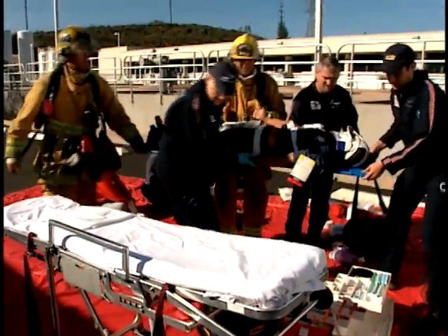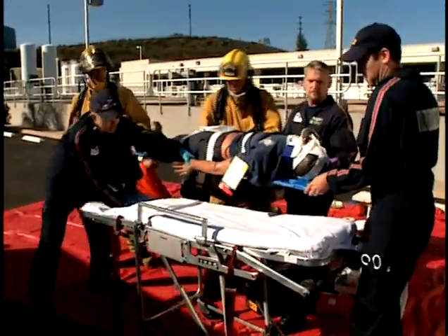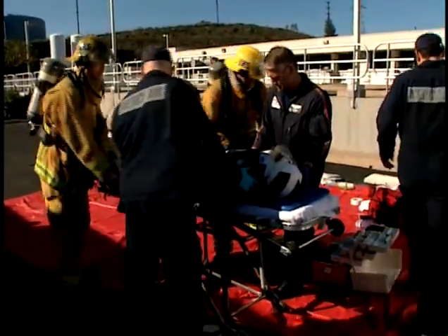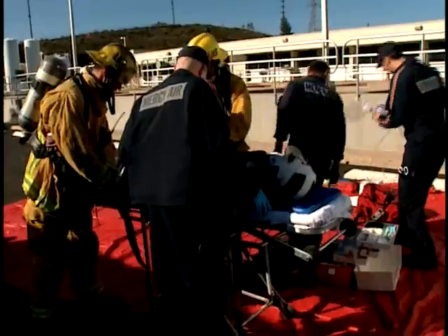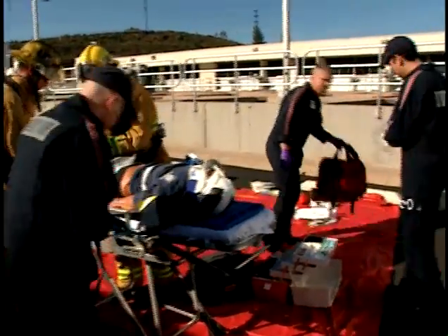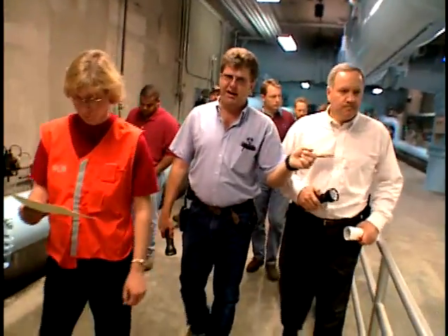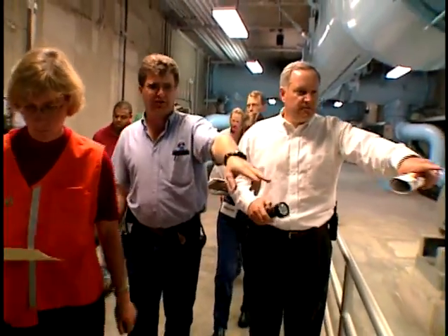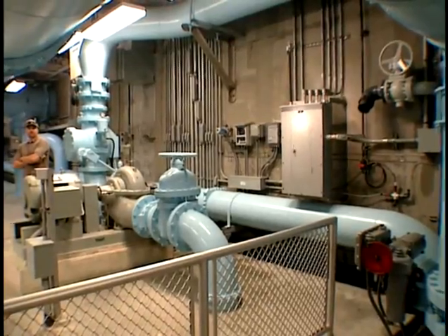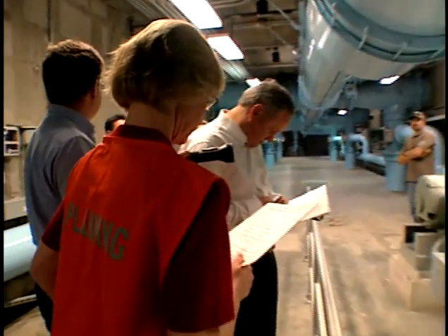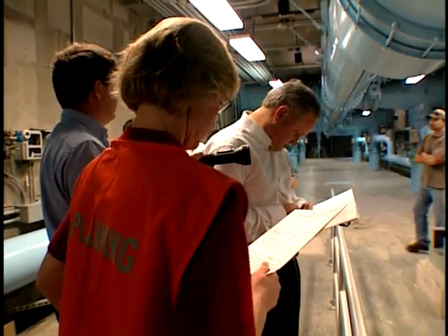Drills, training exercises, or simulations with the local community emergency response planners and responder organizations is one means to obtain better preparedness. And finally, to be certain process safety management is effective, employers must certify that they have evaluated compliance with the provisions of PSM at least every 3 years.